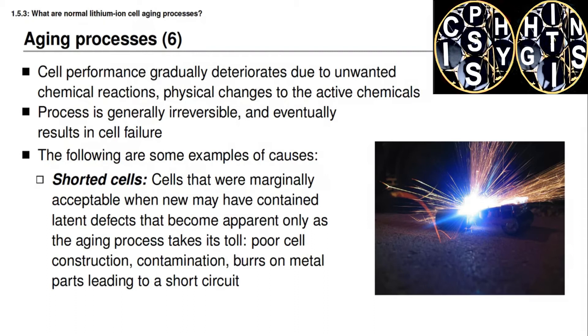Another aging process has to do with the development of an internal short circuit inside the cell. A lithium-ion cell that appeared acceptable when new may have contained some latent invisible defect that becomes apparent only as the aging process unfolds. There might have been poor cell construction, contamination, or metal sharp edges called burrs on the current collectors. Over time, the stresses and strains of each charging and discharging cycle can wear through the separator and lead to contact between the electrodes, causing a short circuit that could result in a fire.